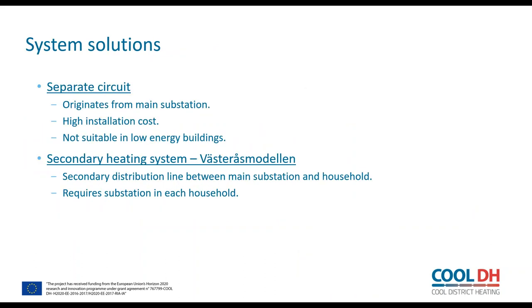Heat-driven appliances can be connected to the district heating grid in a couple of different ways. One way would be to have a separate heating circuit in the same way that there is a circuit for domestic hot water and space heating, which originates from the main substation that is located, for example, in the basement of a building. The solution would be suitable, for example, for existing buildings where there's already similar pipes installed and there's a designated shaft space.